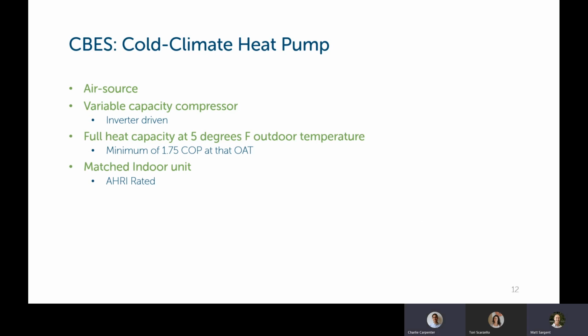Sure. So a new definition for CBES that is going to be quite applicable to this code is cold climate heat pump. And this is a list of what must be required for a piece of equipment to be considered a cold climate heat pump. It needs to be air sourced, have a variable capacity inverter driven compressor. It's got to be able to provide full heating output at 5 degrees Fahrenheit outdoor air temperature, and at that temperature it also needs to have a minimum coefficient of performance of 1.75, and that rating needs to be matched with a specific indoor unit. The outdoor unit and indoor units need to be matched and rated through AHRI, so that you can't be mixing and matching units. They need to be rated together. It's the exact same definition in RBES.